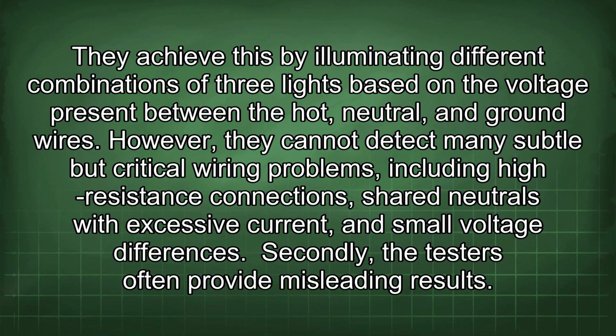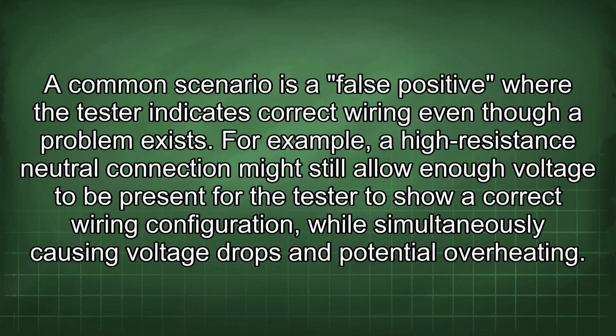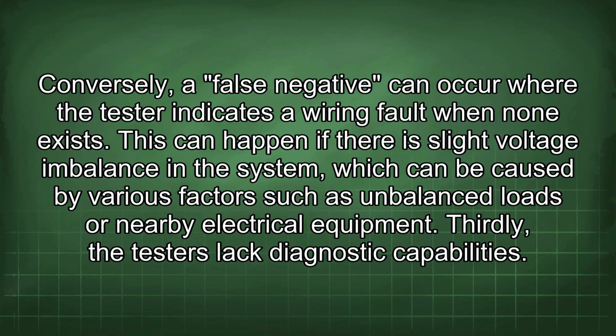Secondly, the testers often provide misleading results. A common scenario is a false positive, where the tester indicates correct wiring even though a problem exists. For example, a high resistance neutral connection might still allow enough voltage to be present for the tester to show a correct wiring configuration, while simultaneously causing voltage drops and potential overheating. Conversely, a false negative can occur where the tester indicates a wiring fault when none exists. This can happen if there is slight voltage imbalance in the system, which can be caused by various factors such as unbalanced loads or nearby electrical equipment.